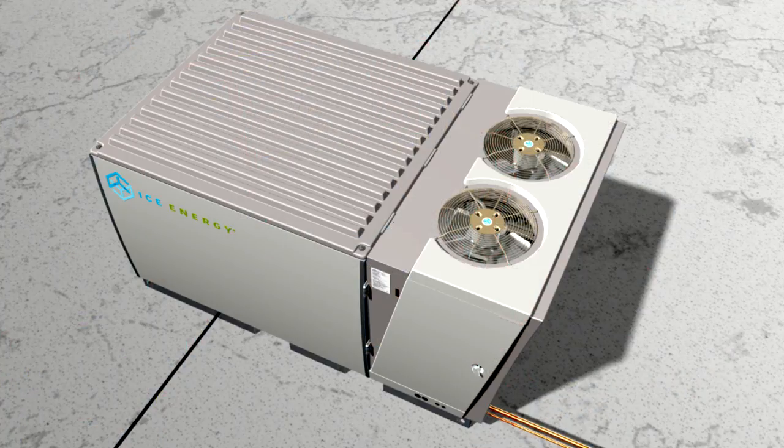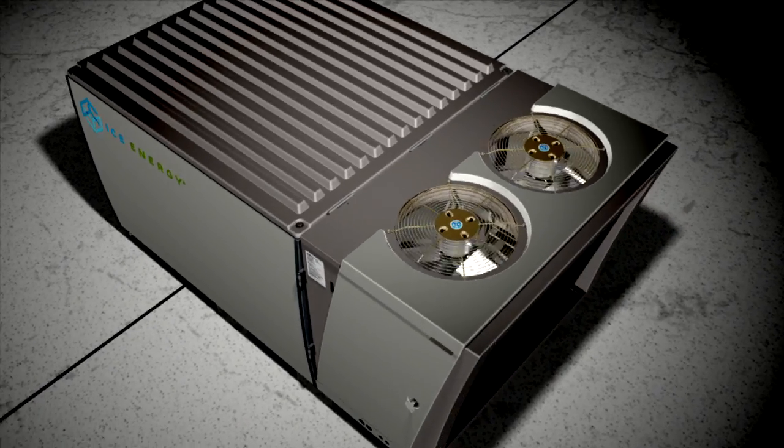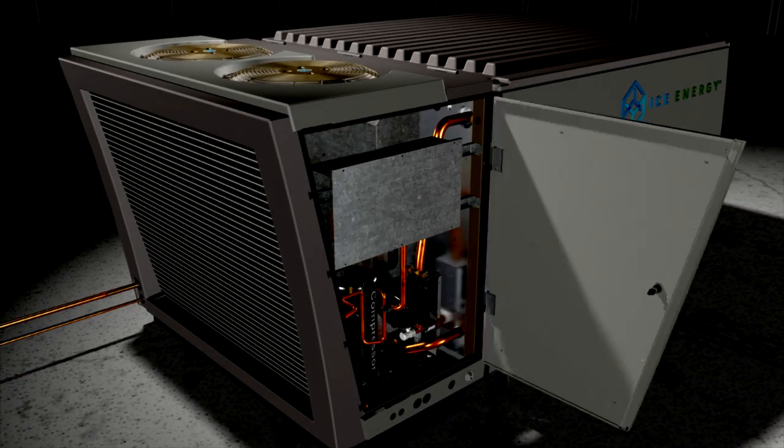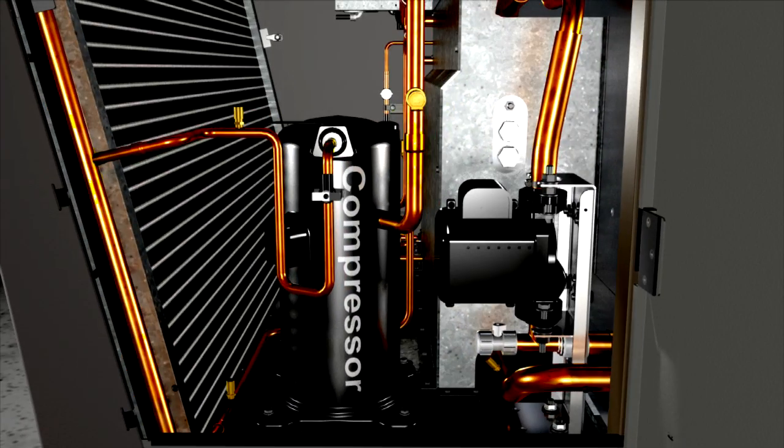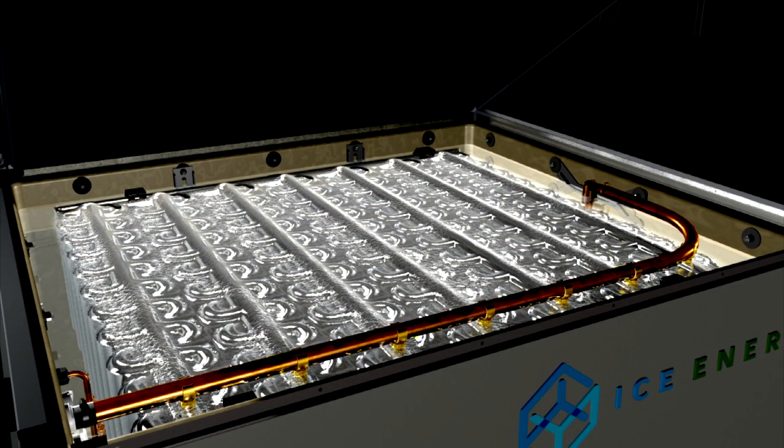The IceBear operates in two basic modes, ice cooling and ice charging. At night, the IceBear goes into ice charging mode. A self-contained ice charging system freezes water in the insulated tank, in effect storing electrical energy in the form of ice.